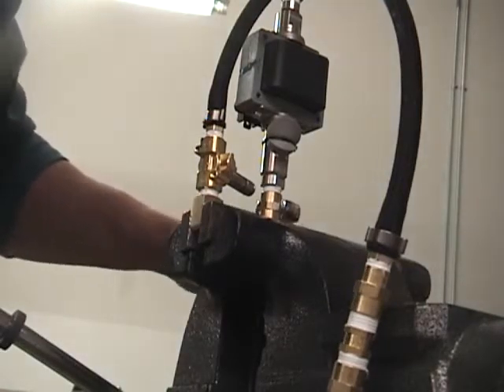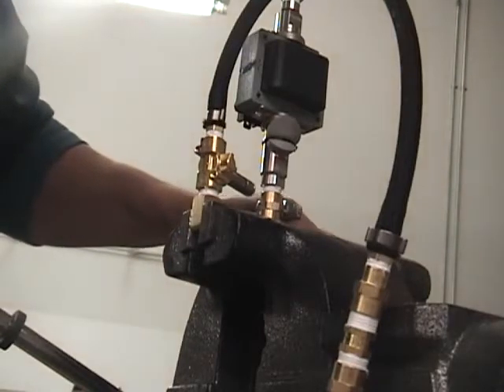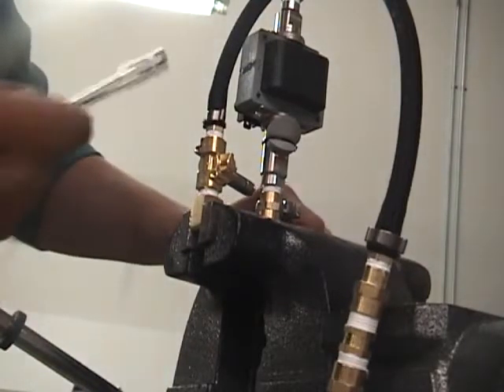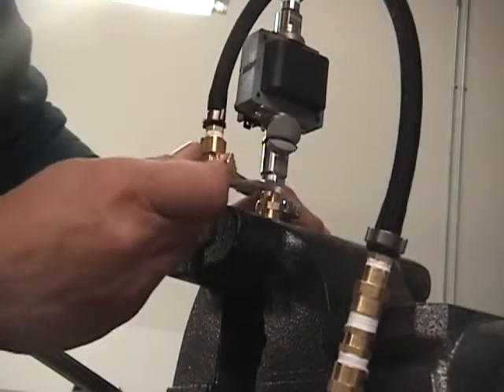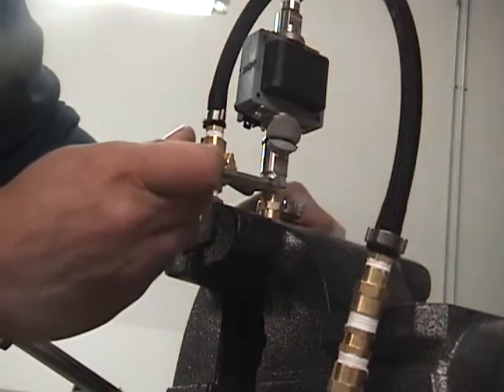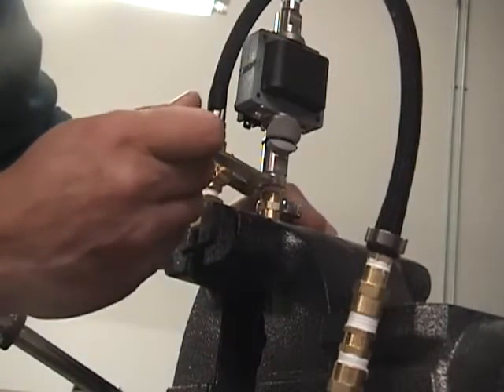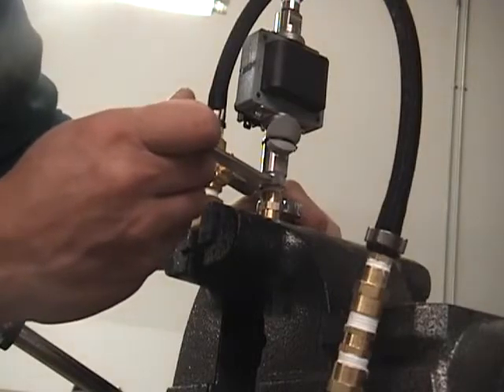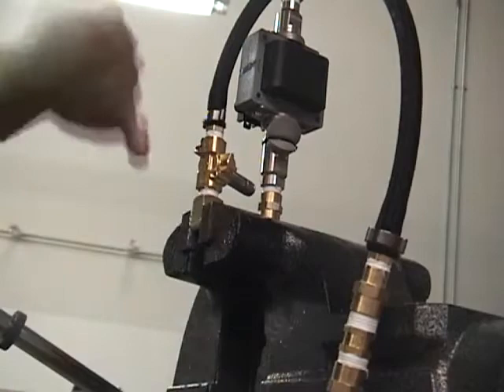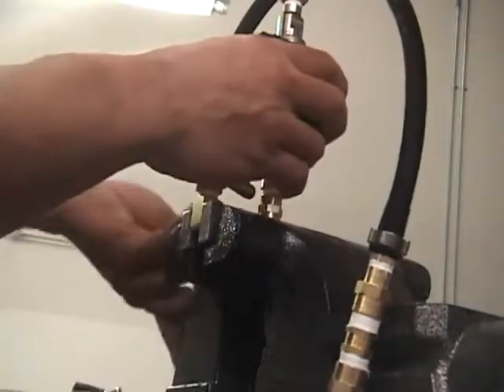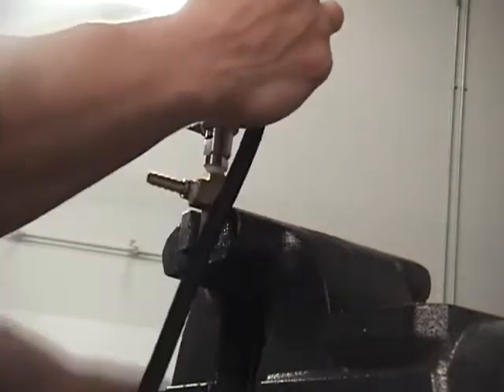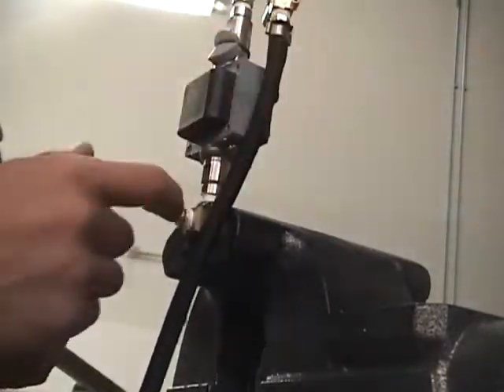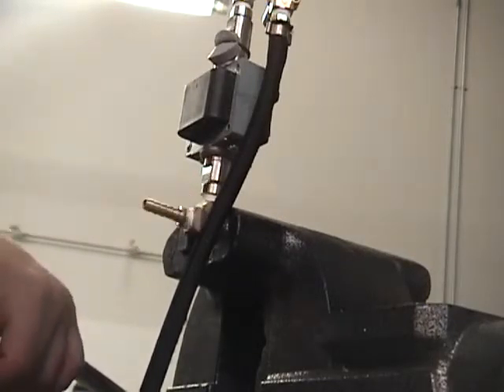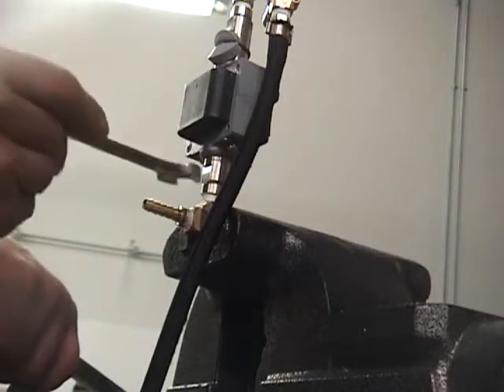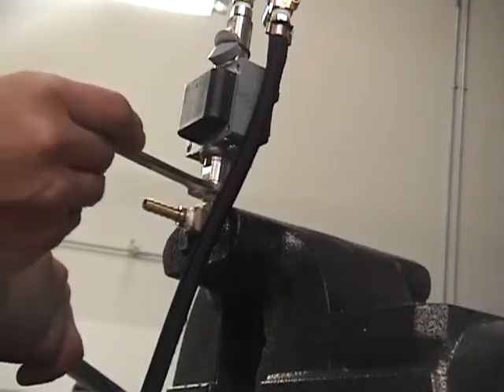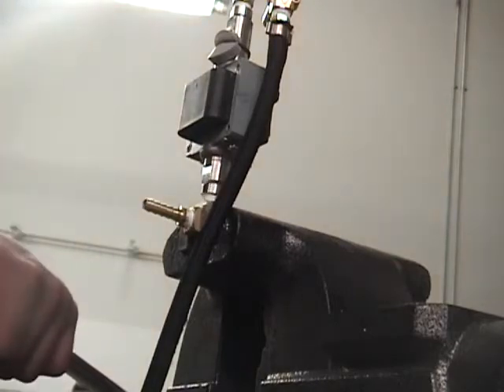Now what you do is this 1/4 inch coupler, you'll want to hold it with a 9/16 wrench, and then to loosen the pump itself, go into the 1/2 inch fitting that is attached furthest from the pump, and then you can loosen up the pump so that it can come off. Once the pump is out of this coupler, you'll need to grab the other part of the pump, which is on this 90-degree angle, and you'll do the same thing with a 1/2 inch wrench. You just loosen it so that you can take the pump itself off of the fitting.